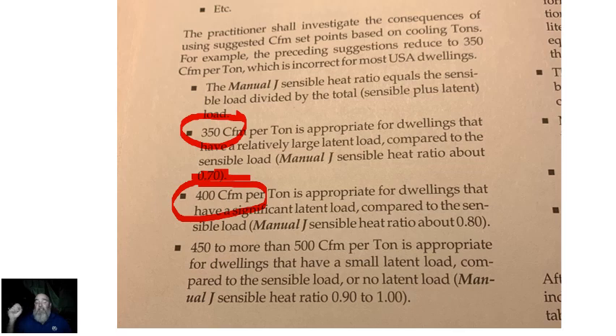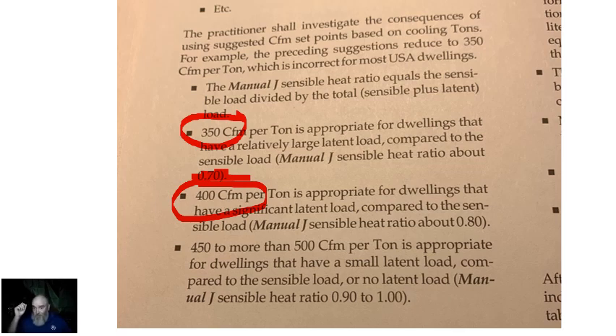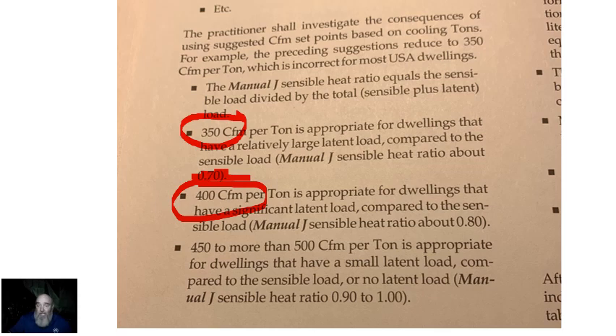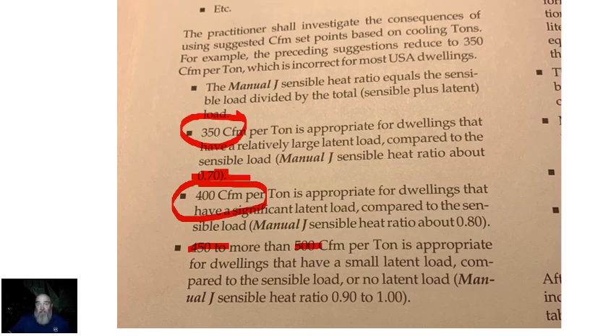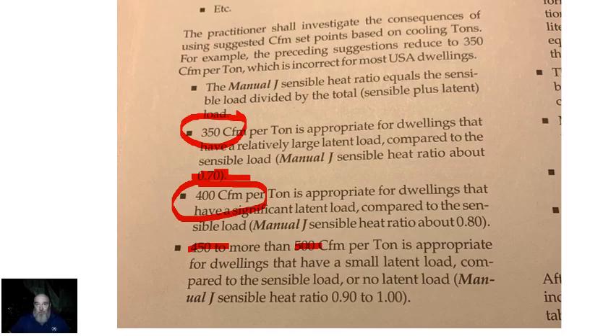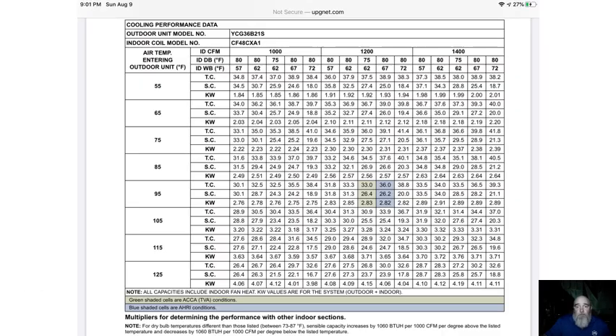At CFM per ton, what we're talking about is specifically sensible capacity, not total capacity, which gets spoken about far too frequently. Bigger airflows like 450 or 500 CFM per ton is going to be appropriate in a typical or better than average house. A house that is tight is going to have a much smaller latent load.